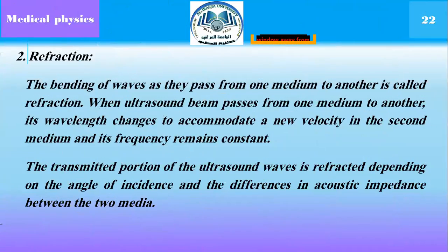Number 2, refraction. The bending of waves as they pass from one medium to another is called refraction. When an ultrasound beam passes from one medium to another, its wavelength changes to accommodate a new velocity in the second medium, and its frequency remains constant. The transmitted portion of the ultrasound waves is refracted depending on the angle of incidence and the difference in acoustic impedance between the two media.